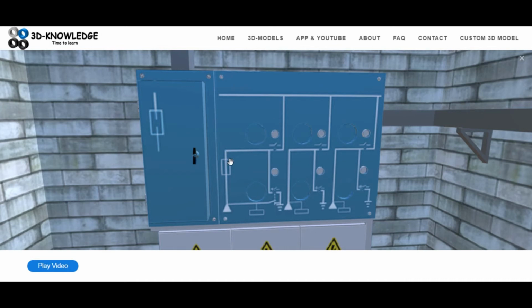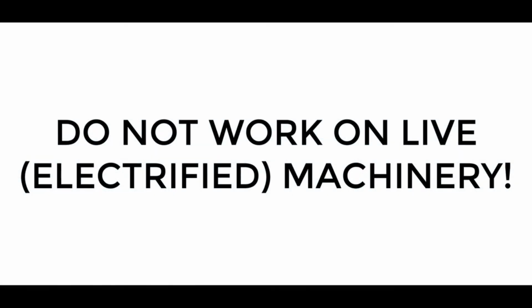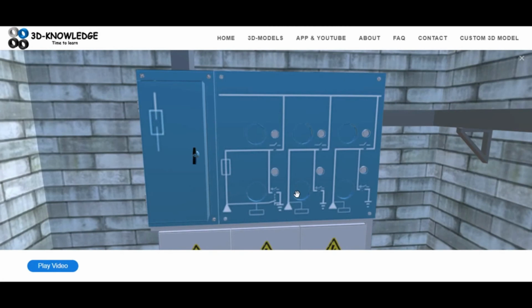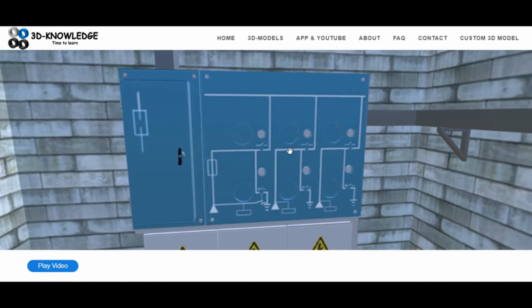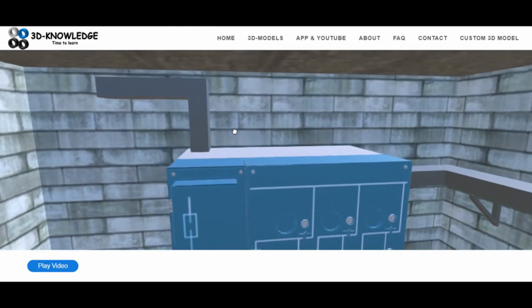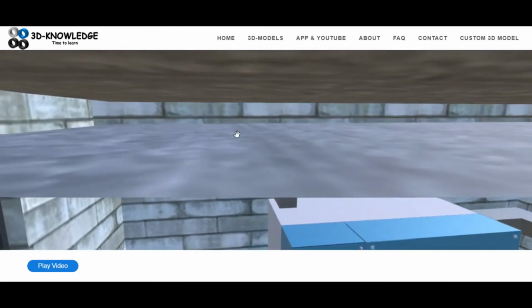In addition, it's also very useful if you're doing maintenance on the generator to isolate it. In fact, it's not just useful, it's a requirement. You'll need to isolate the generator completely so it's safe to work on, and you will isolate it here at the switchgear. Typical voltages here may be 10,000 or 6,000 volts, for example 6 kV, 10 kV, 20 kV, and the type of switchgear used could be air insulated, vacuum insulated, or maybe SF6. At some point we'll make a video on switchgear and explain why we use different types and for what purposes.